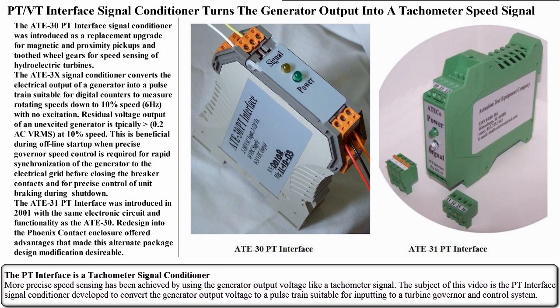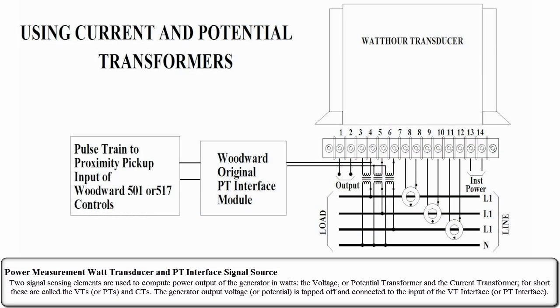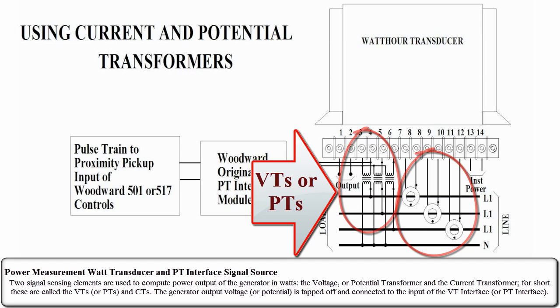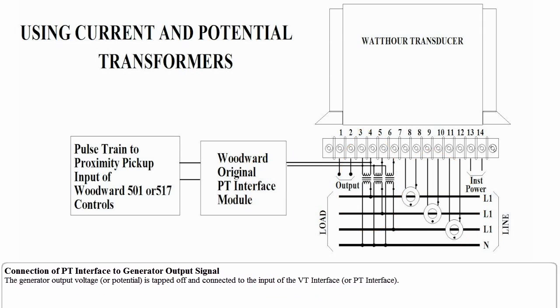The subject of this video is the PT interface signal conditioner developed to convert the generator output voltage to a pulse train suitable for inputting to a turbine governor and control system. Two signal sensing elements are used to compute power output of the generator in watts: the voltage or potential transformer and the current transformer. For short, these are called the VTs or PTs and CTs. The generator output voltage or potential is tapped off and connected to the input of the PT interface.